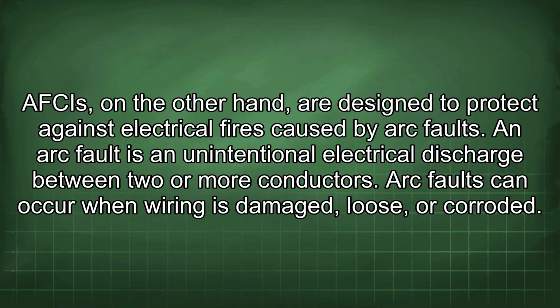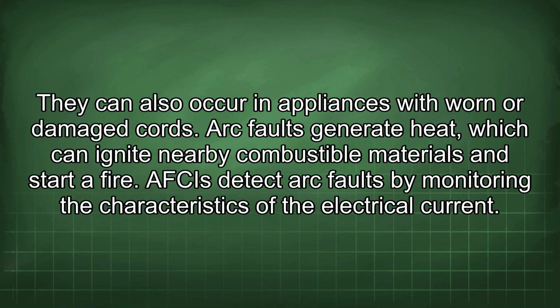AFCIs, on the other hand, are designed to protect against electrical fires caused by arc faults. An arc fault is an unintentional electrical discharge between two or more conductors. Arc faults can occur when wiring is damaged, loose, or corroded. It can also occur in appliances with worn or damaged cords. Arc faults generate heat, which can ignite nearby combustible materials and start a fire.